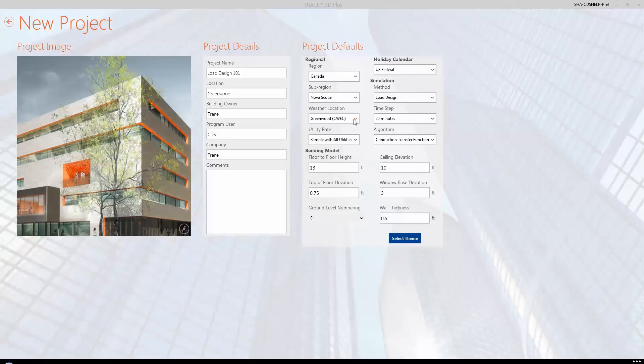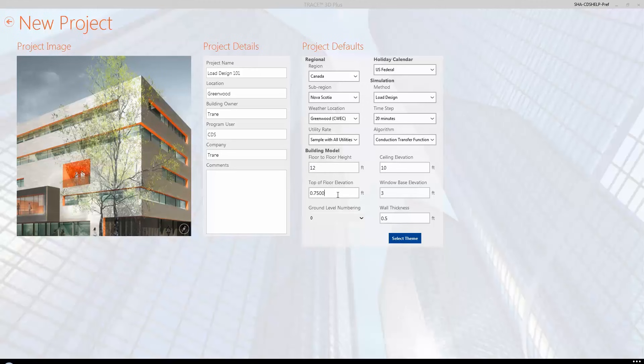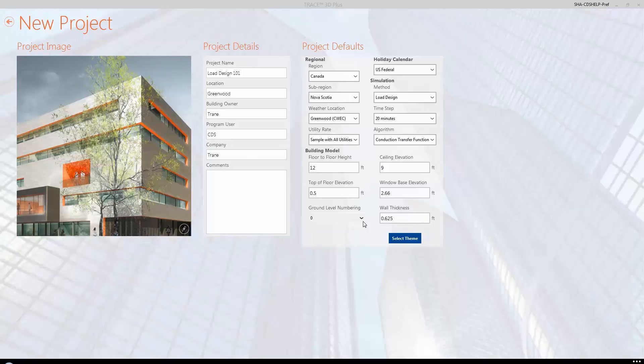Our example will use the parameters listed on the project information document. The Load Design 101 Exercise Information document gives us a floor to floor height of 12 feet, which we will enter here. Next, enter the ceiling elevation as 9 feet, the top of floor elevation as 0.5 feet, and the window base elevation as 2.66 feet. Finally, since our wall thickness is 7.5 inches, enter the value as 0.625 feet.